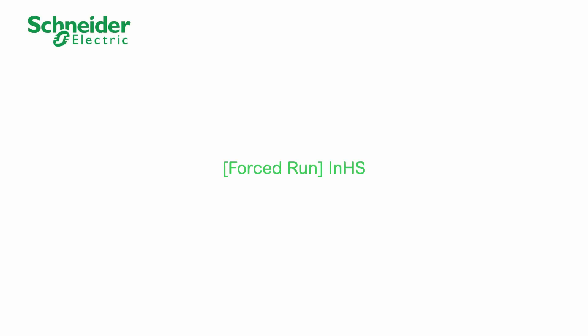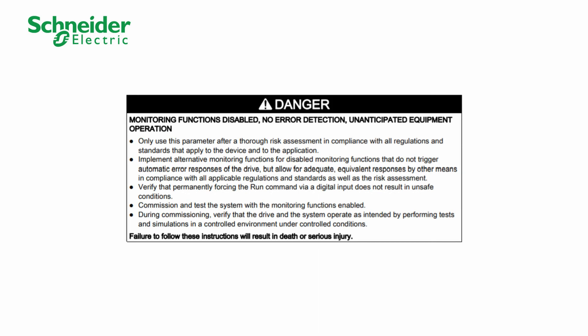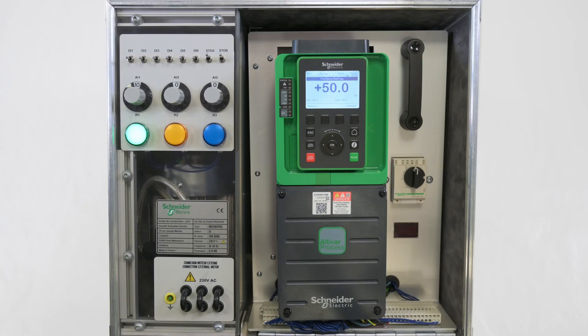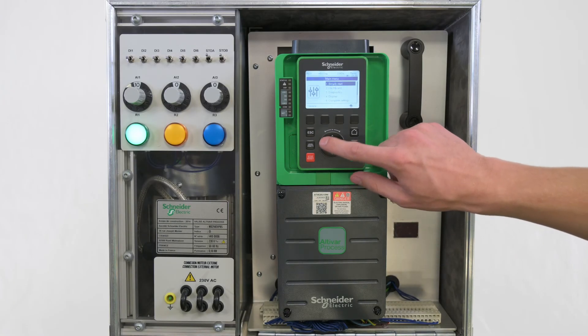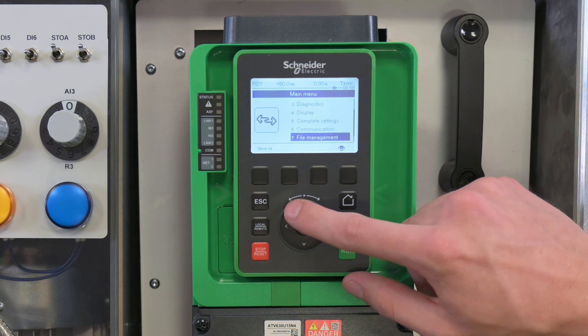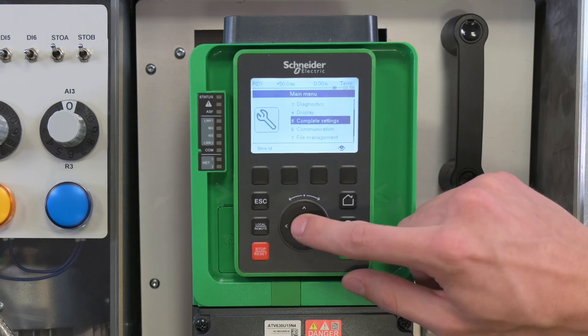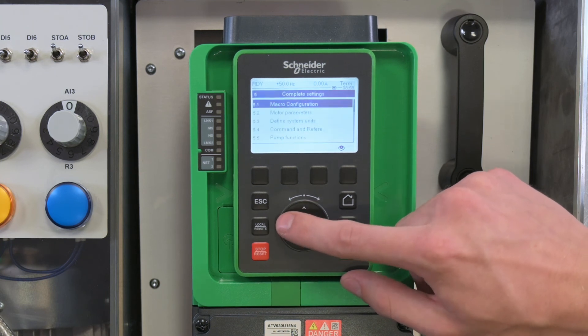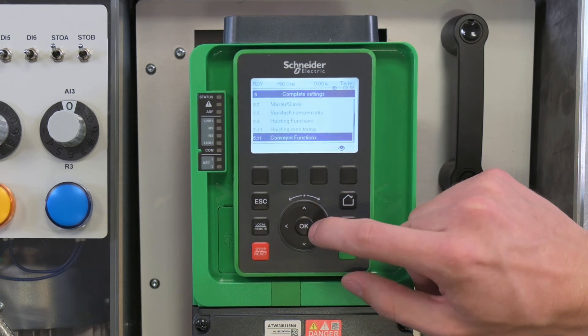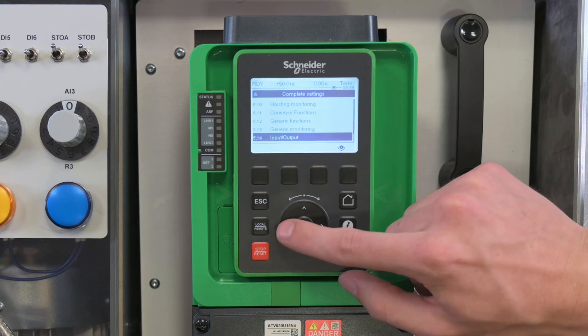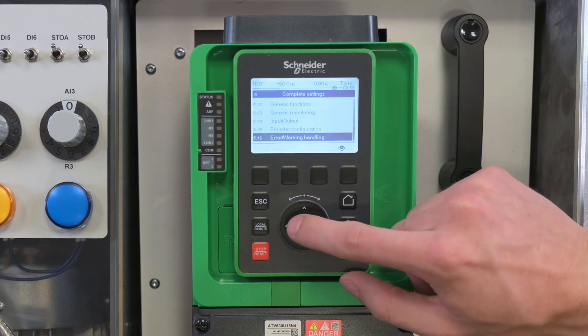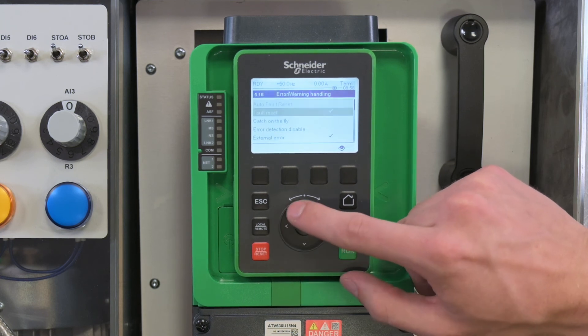Forced run. Before using forced run, be sure to read and fully understand the following safety message. By setting up forced run, your motor will run without triggering certain errors. First, enable forced run and select the direction of rotation — forward or reverse — to apply in forced run mode.